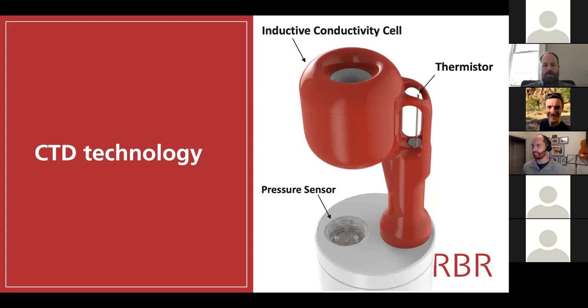Salinity, and density, speed of sound, all the other derived parameters, does have a dependence also on pressure. And so if you're going to profile an instrument through the water column, not only do you need pressure to know where you are in the water column in the first place, but you also need it to correctly calculate salinity, even though that dependence is fairly small. When you're on a mooring system, you can simply put in a static value into the instrument and say, you were deployed at 100 dbar, and you can get away with an instrument that purely has C and T. You don't need pressure if you're not going to change it over the lifetime of the deployment. But for every vehicle, or let's say vehicular and profiling applications, putting pressure on is essential.